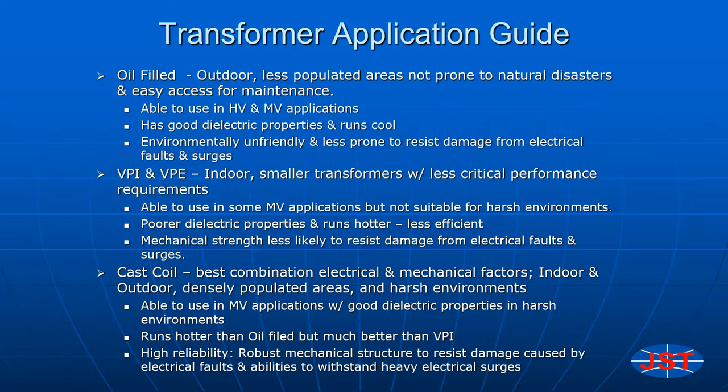Oil-filled are well suited for outdoor applications in areas that are less populated and not prone to natural disasters. There should also be easy access for maintenance. VPI and VPE are suited for indoor applications where the performance requirements are not as critical. Cast coil can provide a very good combination of electrical and mechanical factors that lend themselves to both indoor and outdoor applications in densely populated areas as well as the ability to operate in harsh environments.